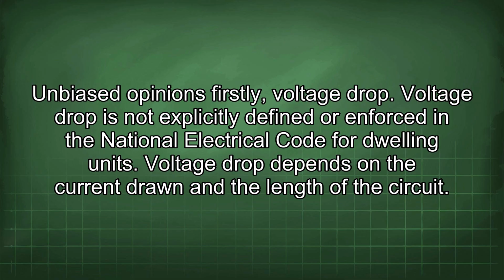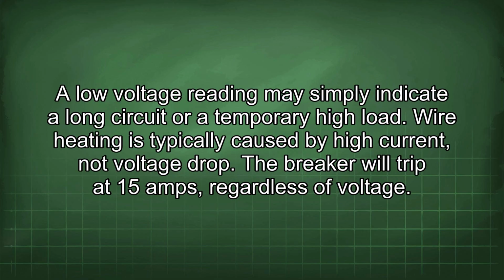Voltage drop is not explicitly defined or enforced in the National Electrical Code for dwelling units. Voltage drop depends on the current drawn and the length of the circuit. A low voltage reading may simply indicate a long circuit or a temporary high load. Wire heating is typically caused by high current, not voltage drop. The breaker will trip at 15 amps, regardless of voltage.